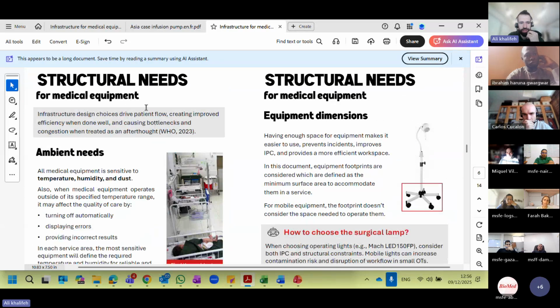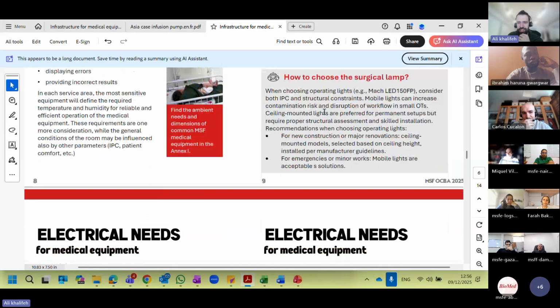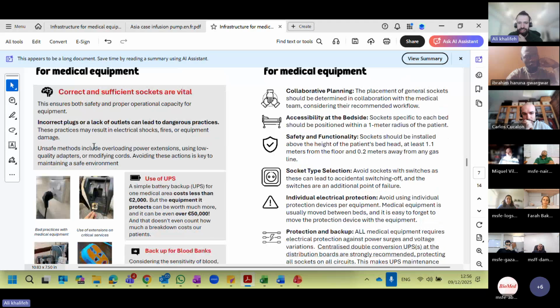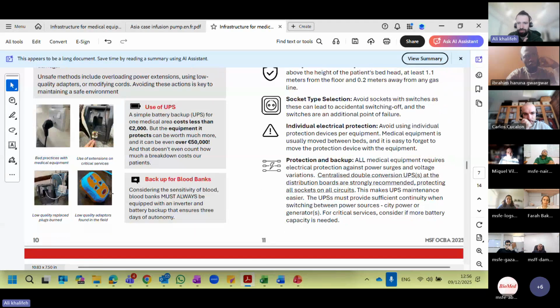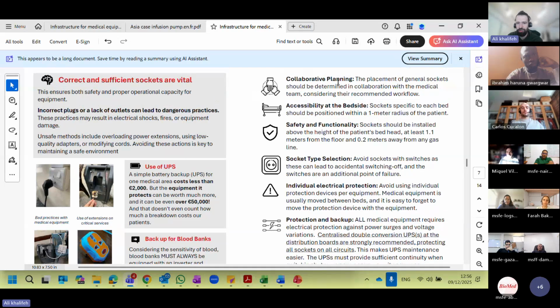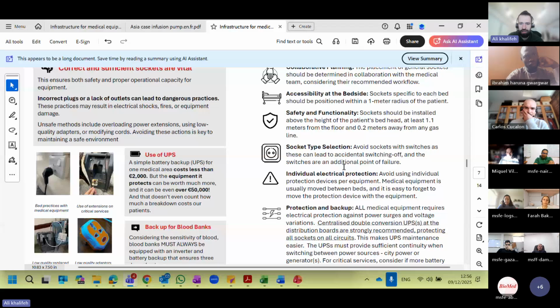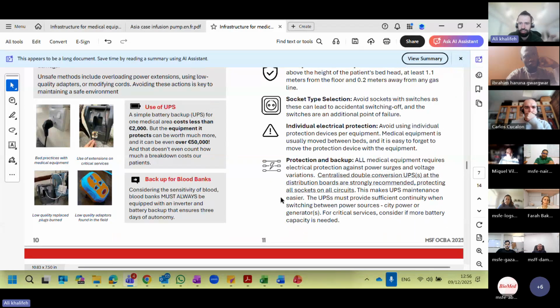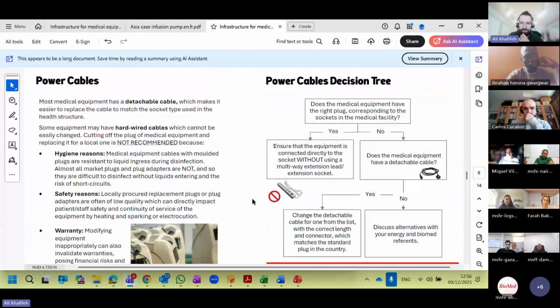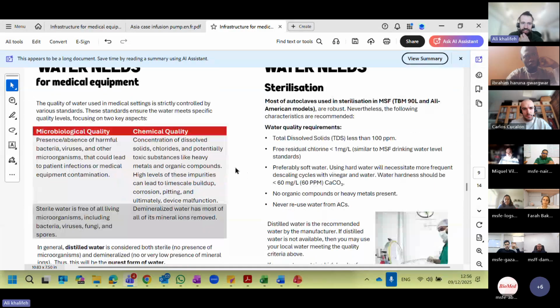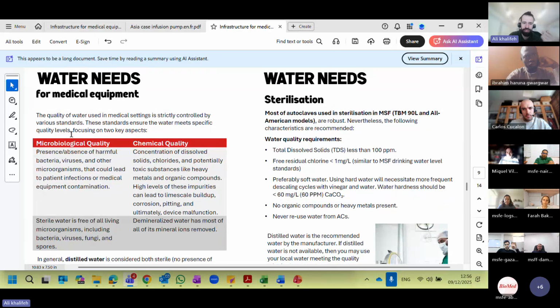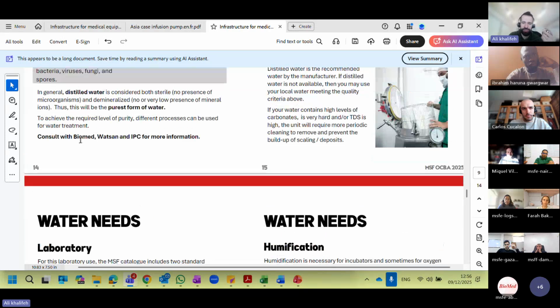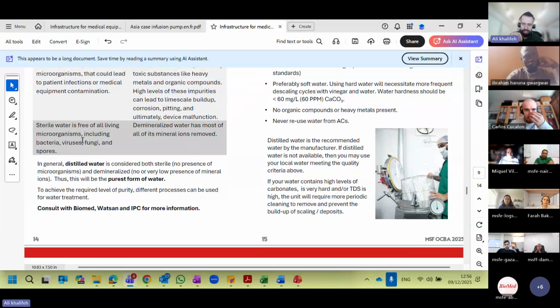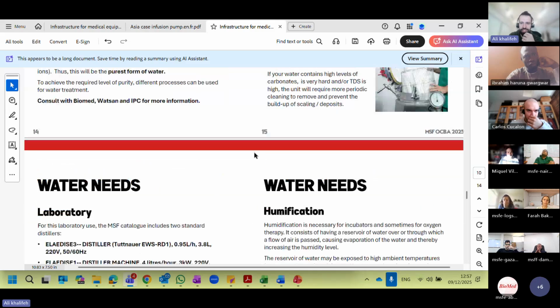For the structural needs of medical equipment, we have here the ambient needs and equipment dimensions, and here you can see all the needs. For electrical needs, we have in detail where equipment needs a UPS, which type of sockets are needed, and all the recommendations about collocation, accessibility, position of the sockets, type of the sockets based on the country, and the electrical protection and backup. And here also for the power cable, a decision tree: which power cable needs to be used and what safety measures need to be taken. And also for the water needs, we have different types of water for sterilization, for laboratory, for humidification. Each type of equipment needs a dedicated type of water: distilled water, sterile water, the difference between distilled and sterile water, all this, okay?